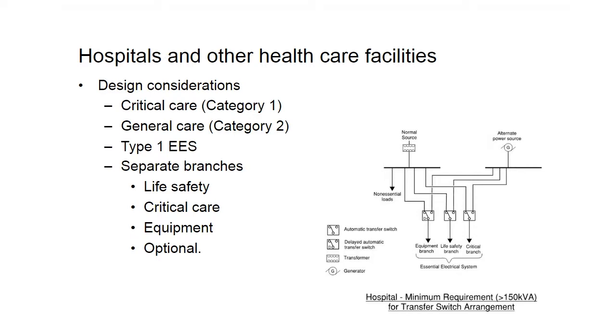So in a general care area, the space is where the failure of the equipment or system is likely to cause potentially a minor injury to the patients or other occupants within the space, whereas a critical care space is one where the failure of equipment or systems is likely to cause major injury or potentially even death to the patients, staff, or visitors in these areas. So these are typically spaces where the patients are intended to be subjected to invasive procedures and/or connected to life support equipment. So obviously, in a critical care area, we're required to have a type 1 emergency electrical system or essential electrical system.